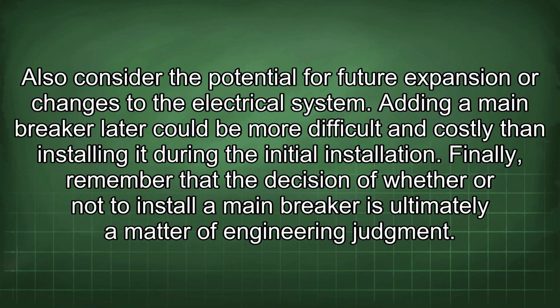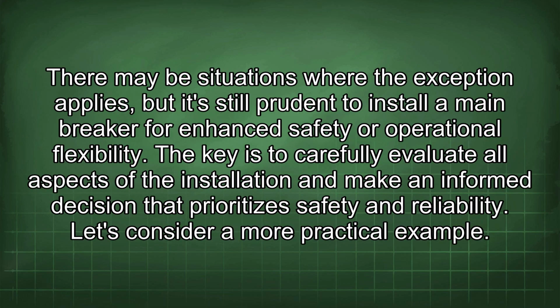Also consider the potential for future expansion or changes to the electrical system. Adding a main breaker later could be more difficult and costly than installing it during the initial installation. Finally, remember that the decision of whether or not to install a main breaker is ultimately a matter of engineering judgment. There may be situations where the exception applies, but it's still prudent to install a main breaker for enhanced safety or operational flexibility. The key is to carefully evaluate all aspects of the installation and make an informed decision that prioritizes safety and reliability.